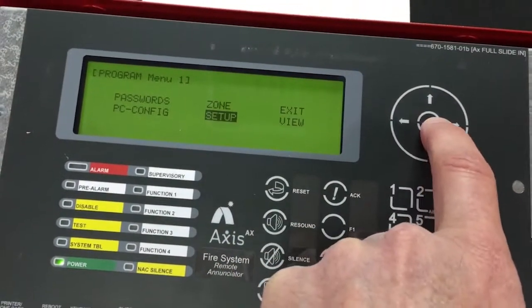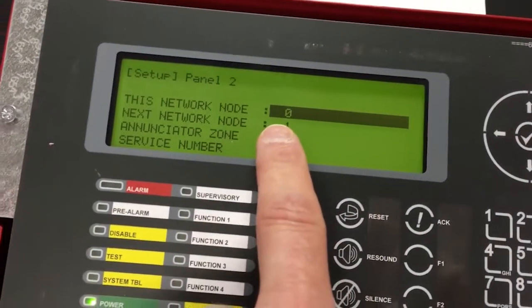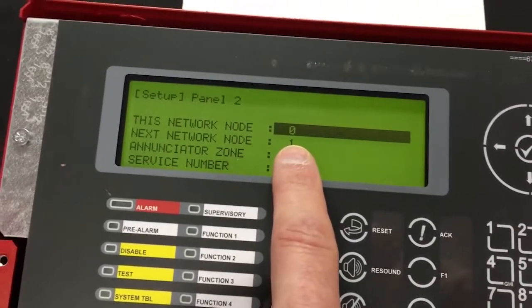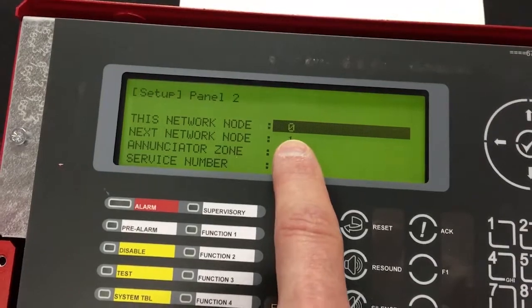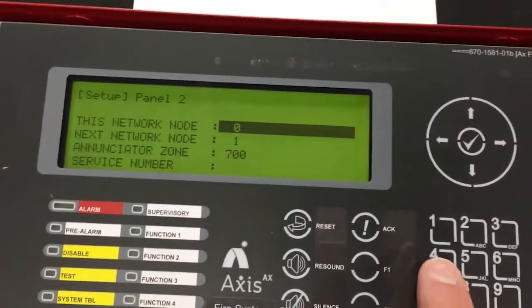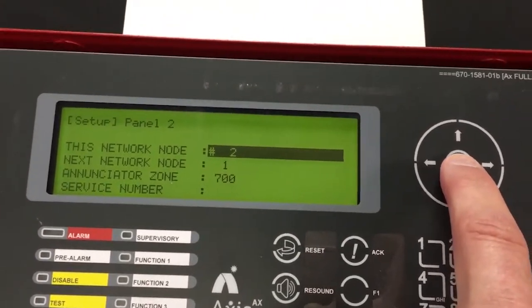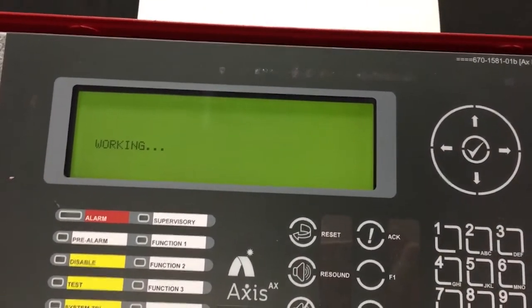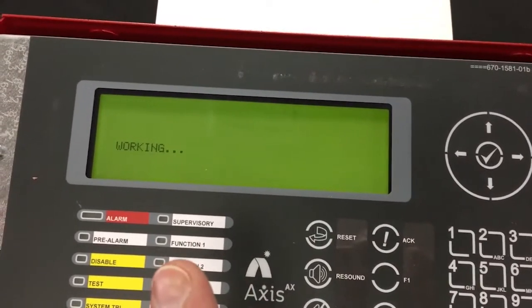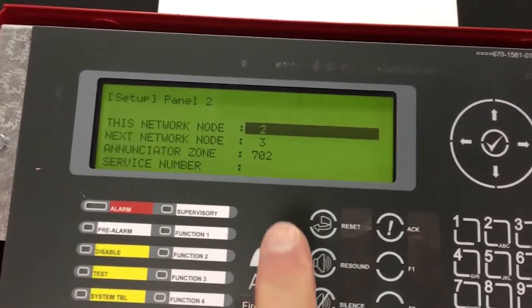You'll notice that this says node number zero, next node is one — so it doesn't know anything. We know the fire panel was node number one looking for node number two, so I'm going to tell this annunciator that it's node number two and hit the check mark. When we do, it'll come back and say that it's working. When it's all done, it's learning that it's number two, and its next node number is going to come back as node number three.